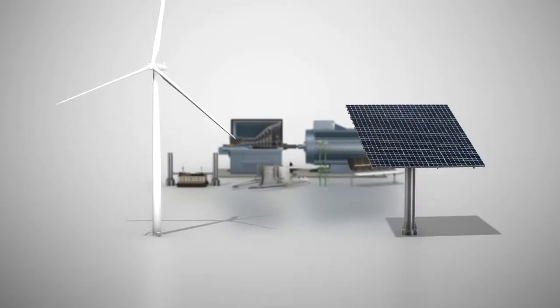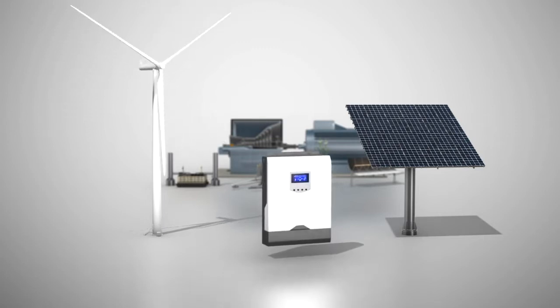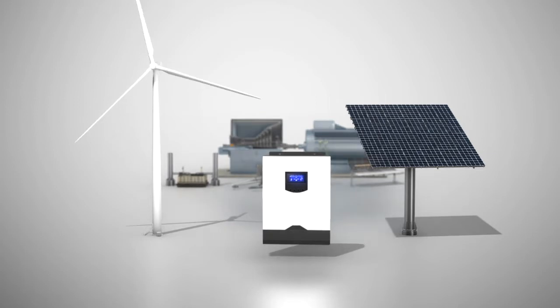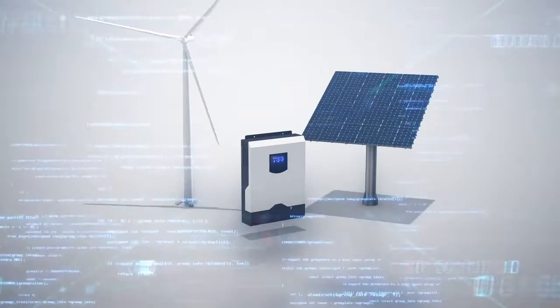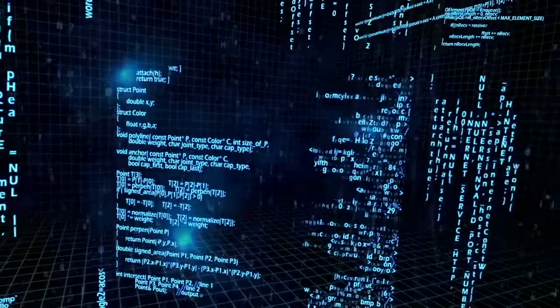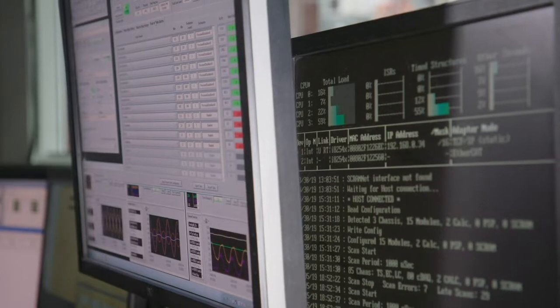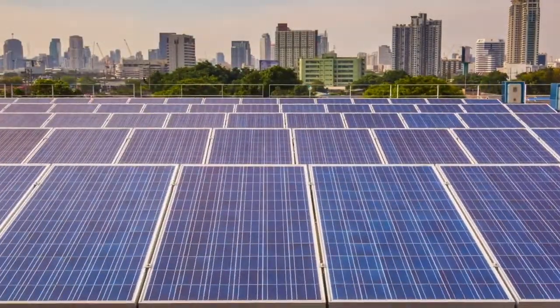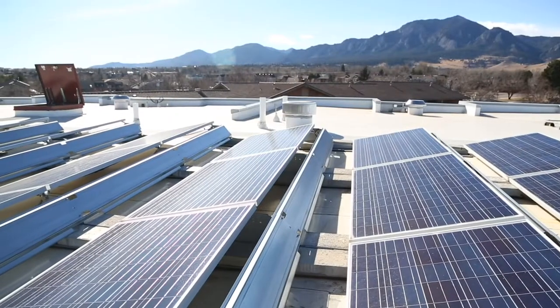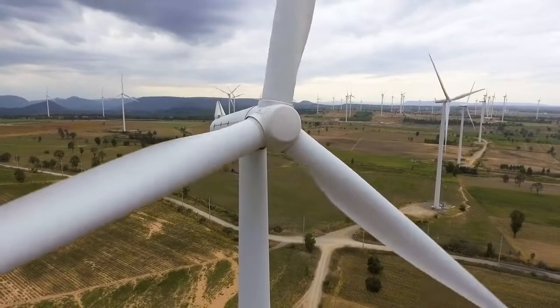The traditional inverters that are on the grid today are what are called grid following. Those are based on the assumption that you have this stable grid that is already provided to you. A grid forming inverter completely dispenses away with the notion that you need an energized, stable system that you're connecting to and following on.